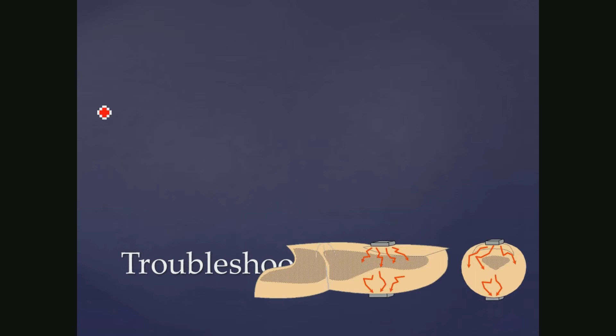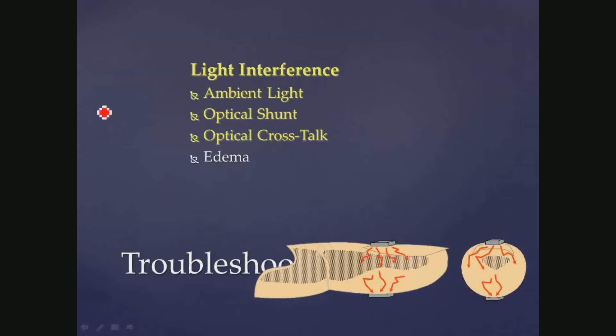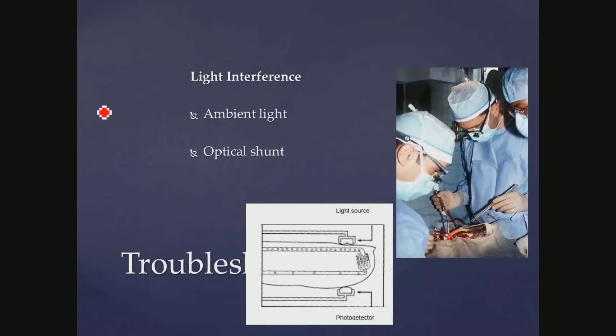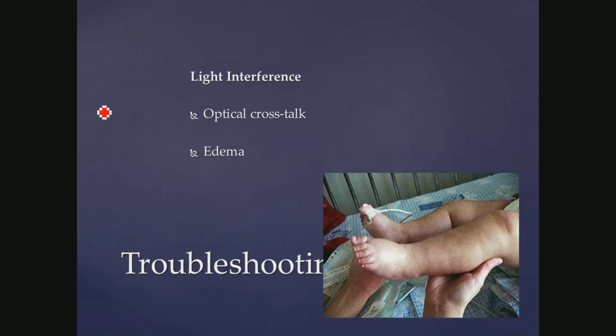Common conditions that can cause problems: light interference, any other light other than what is there will allow for an error in reading because it could be picked up on the photo detector. Edema was there because typically with edematous tissue, the sensor doesn't fit really well, as it has the two LEDs and the photo detector opposite each other. You can see this edema, the poor swollen leg there and foot.